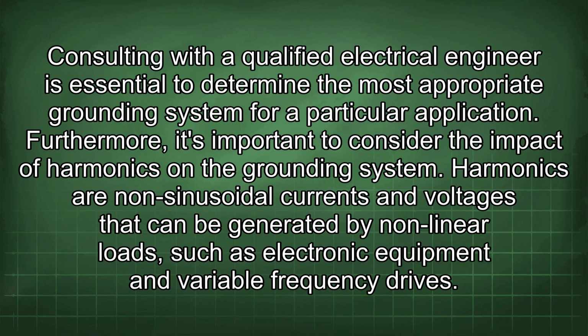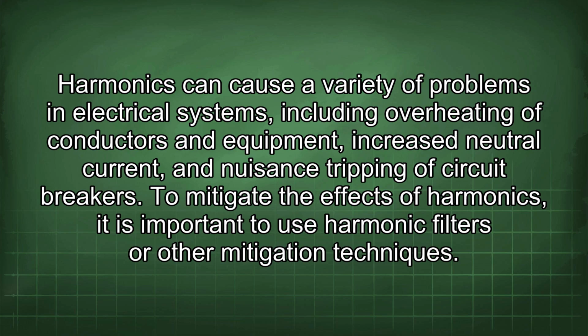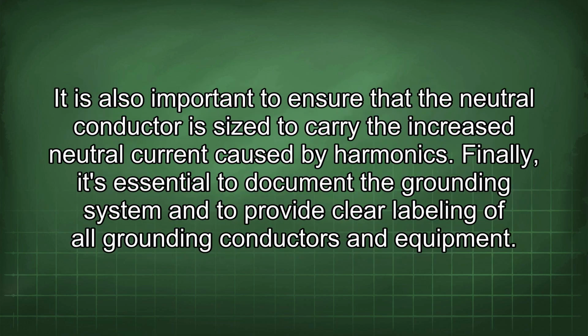Furthermore, it's important to consider the impact of harmonics on the grounding system. Harmonics are non-sinusoidal currents and voltages that can be generated by nonlinear loads, such as electronic equipment and variable frequency drives. Harmonics can cause a variety of problems in electrical systems, including overheating of conductors and equipment, increased neutral current, and nuisance tripping of circuit breakers. To mitigate the effects of harmonics, it is important to use harmonic filters or other mitigation techniques.